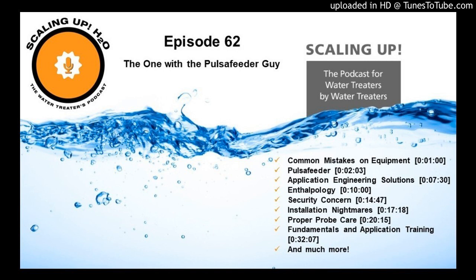Yes and no. The glass permeable pH and the same exact probe with a platinum rod sticking out of it for ORP is largely unchanged. Fundamentally, the same exact technology is used. I would say that electronics have gotten better. The isolation on electronics, the precision of power supplies, and making certain analog to digital sensing equipment more cost affordable has definitely bridged the gap a little bit. But the actual analog sensing element hasn't changed in our industry, at least.